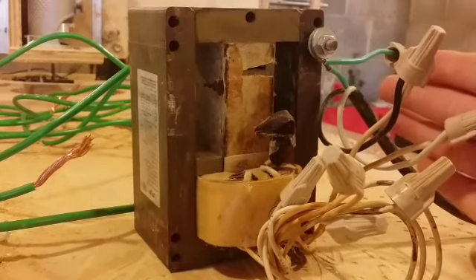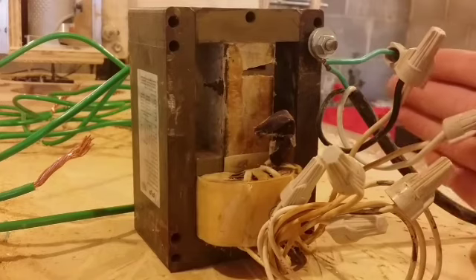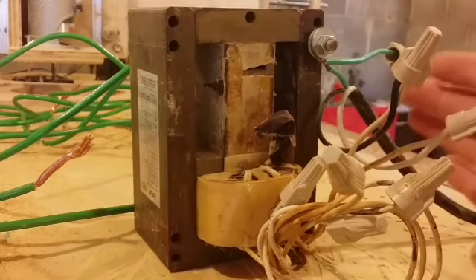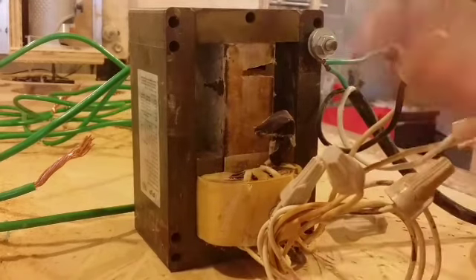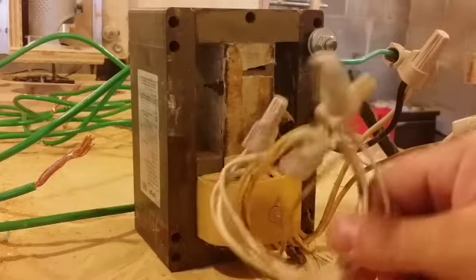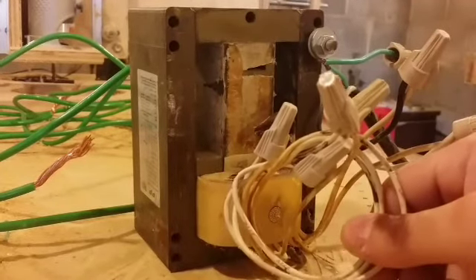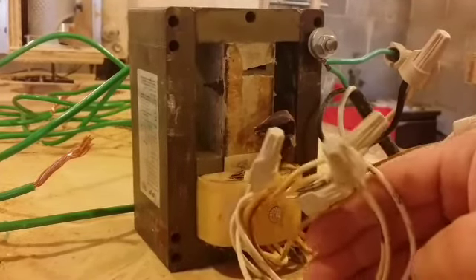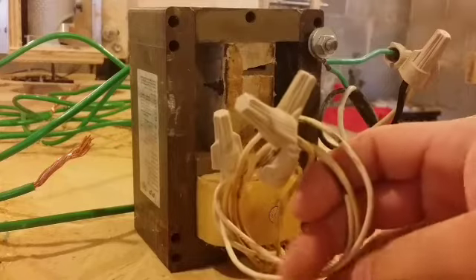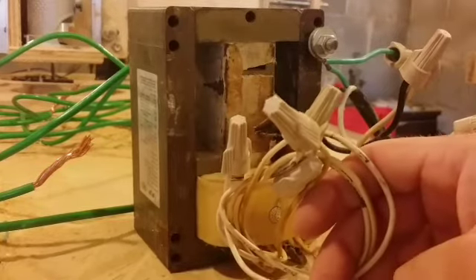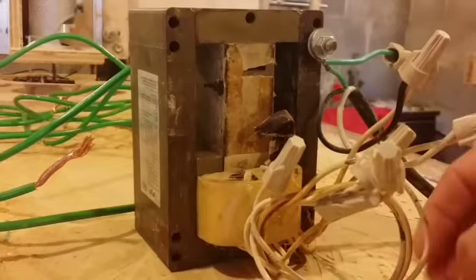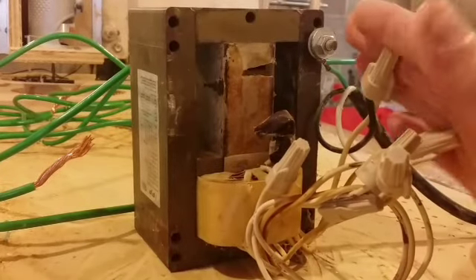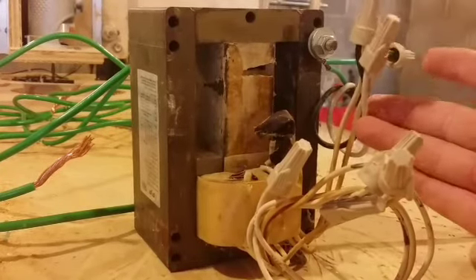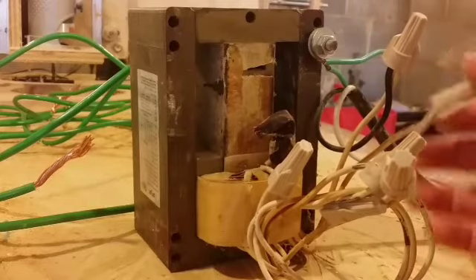So what this does is, if you supply a voltage to the common and one of the taps, one of the 5 taps, the rest of the taps aren't supposed to be used in the HID fixture, but the other taps will have their rated voltage appear on them due to the action of the auto transformer. So in this setup, I'm bringing 120 volts in, common, and 120.